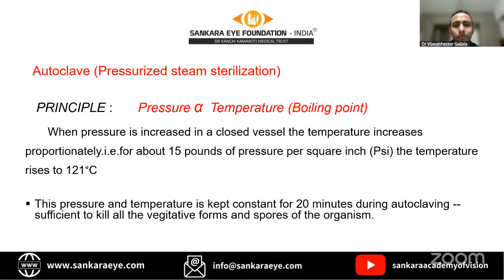Not going into the mechanism of this autoclave proper. If you want to reduce this contact time from 20 minutes to 10 minutes, we need to increase the temperature. For that, automatically we need to increase the pressure. For 30 pounds pressure, the boiling point will go to 132 degrees centigrade. At that level, 10 minutes of contact period is sufficient to kill all the spores. That's how autoclave works.